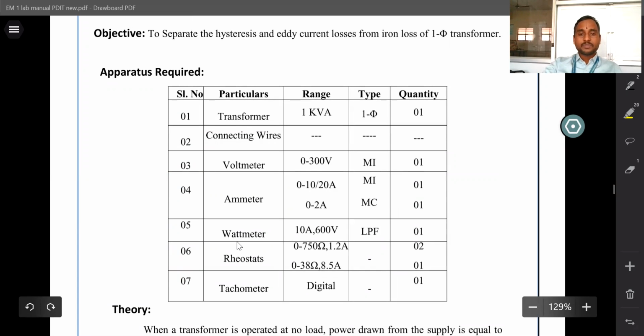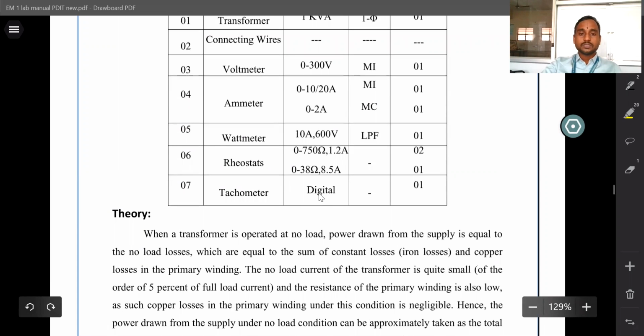And a wattmeter, 10 amps 600 volt, low power factor, because we are connecting the transformer in open circuit, so we are not connecting any load. Two rheostats are required: 750 ohm is one, and another one is a 38 ohm rheostat. And a digital tachometer is required for the speed measurement.